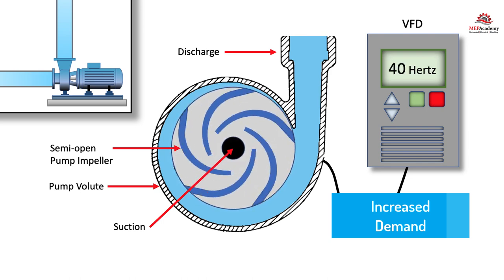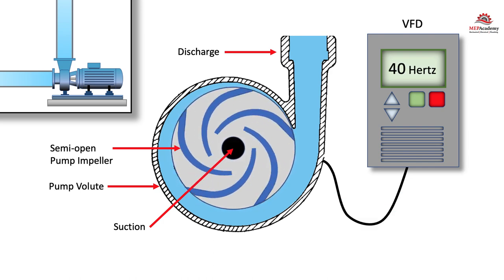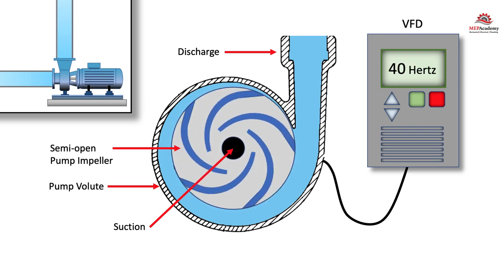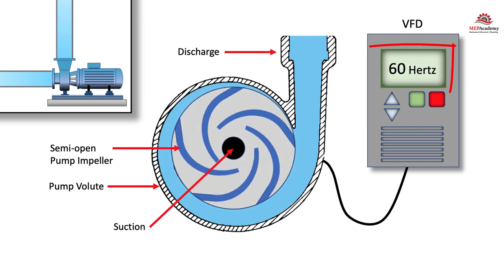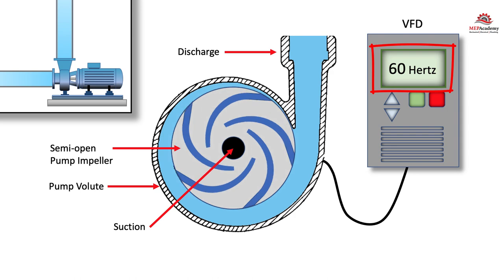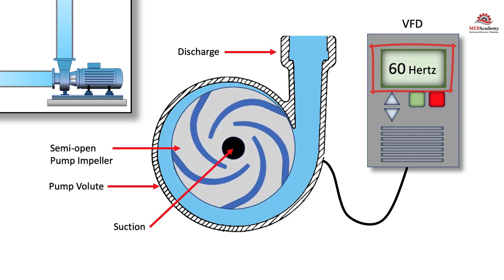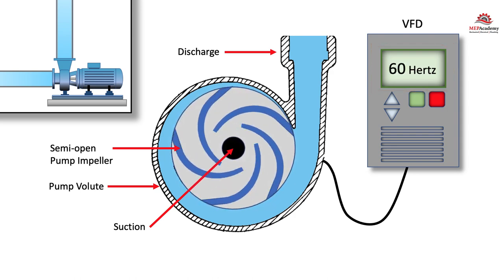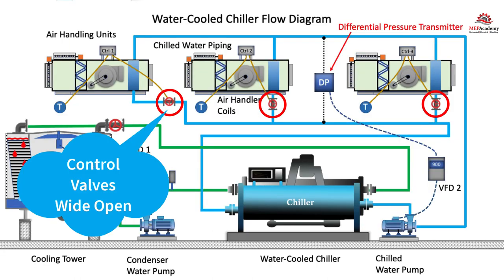And as the demand increases the VFD will send a signal to the motor to speed up. Like here this is full speed so they're getting the full GPM to the system which probably means that all the air handler coils, fan coils, all the control valves are open wide. It's a very hot day. They want chilled water at full flow.